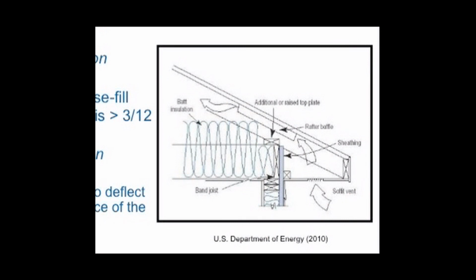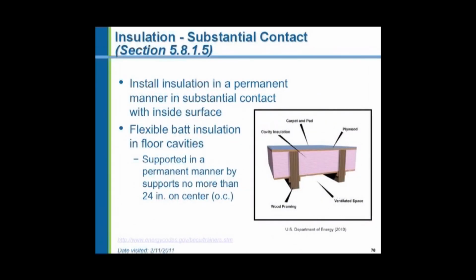If you have eave vents, in other words soffit vents here letting attic ventilation up to a ridge vent, you have to have little baffles to prevent the insulation from closing off the ventilation path. And there are some exceptions, talking about a metal building. Insulation in the floor has to be in substantial contact with the underside of the floor surface, and it has to be supported in a permanent manner. Can't rely on friction to keep it from falling out.